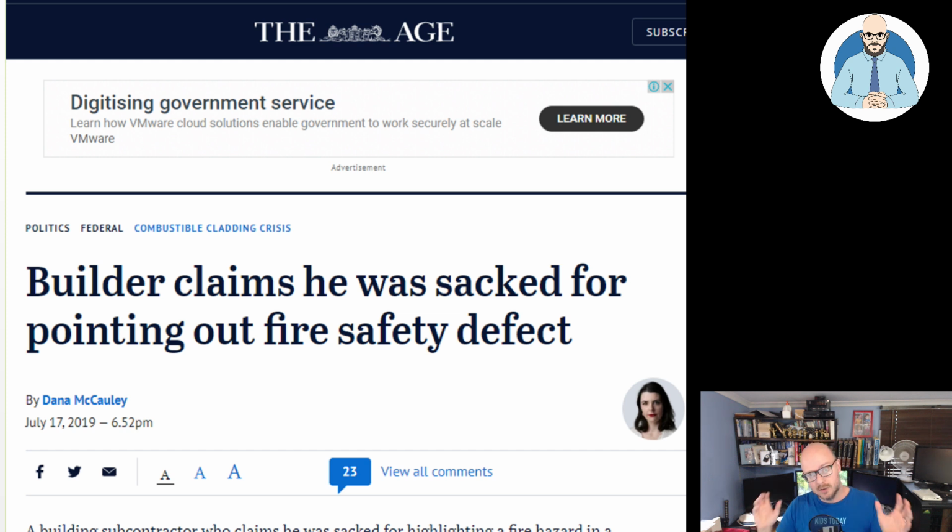And there's fire ratings in the walls between the different apartments, between the apartments and the corridor outside. That means if you live in an apartment, go have a look at your door going out into the corridor. You should see it should be a fire rated door, and there should be a little metal plaque on there telling you what's required. And those doors have much more onerous performance requirements than just the normal door.